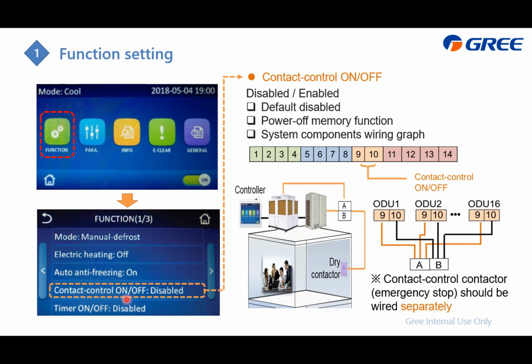Contact control on/off. This means if you enable it, then we allow you to control this chiller, an A or B series chiller, from the dry contactor. And of course, you need to do the external wiring, and this wiring should be separated for different chillers.